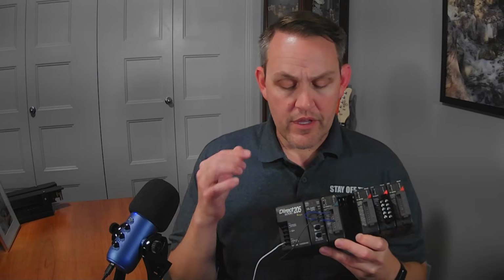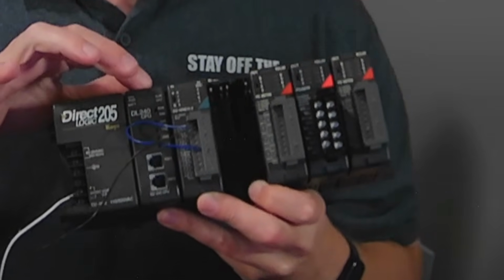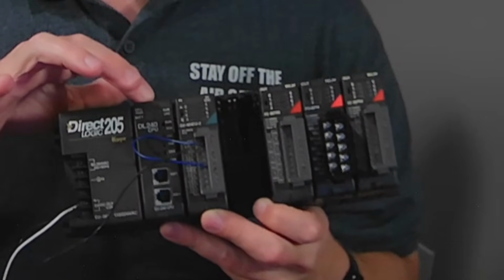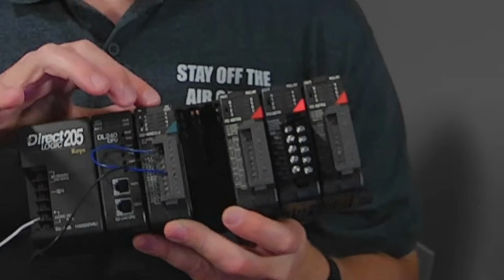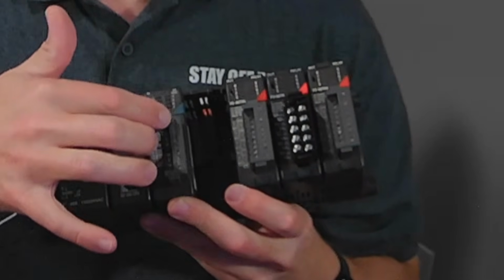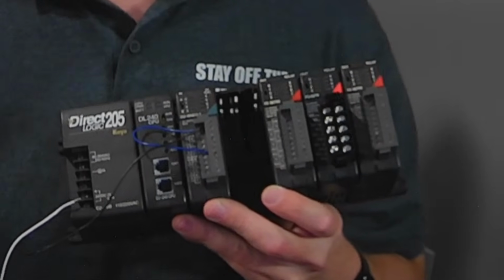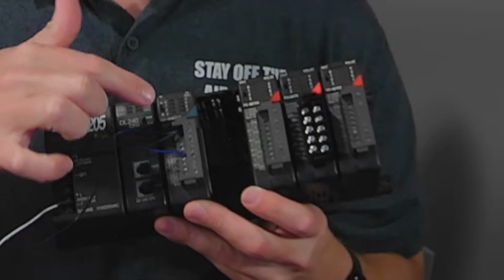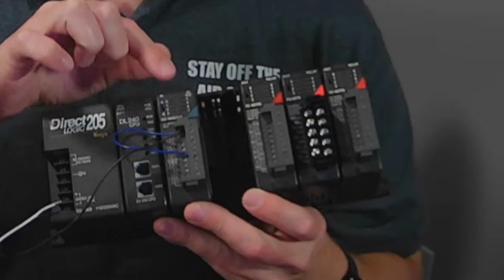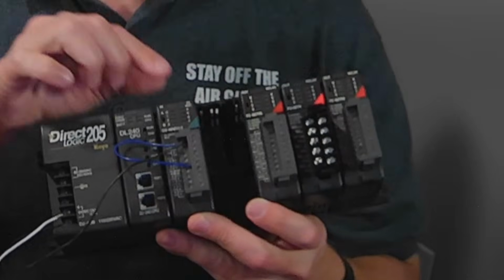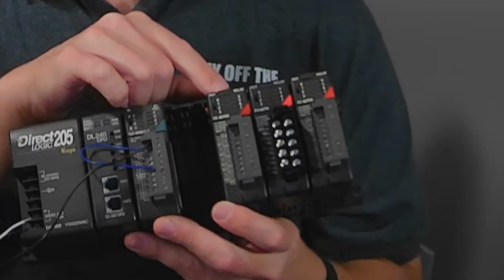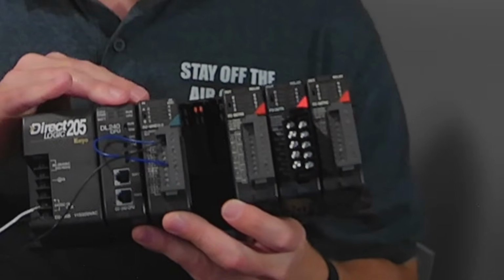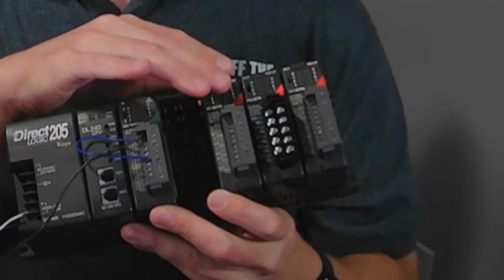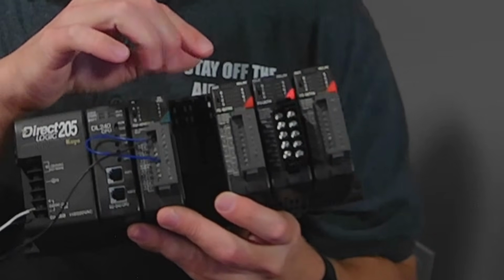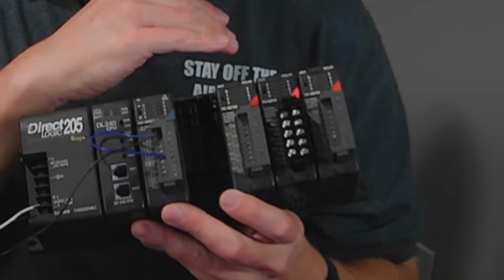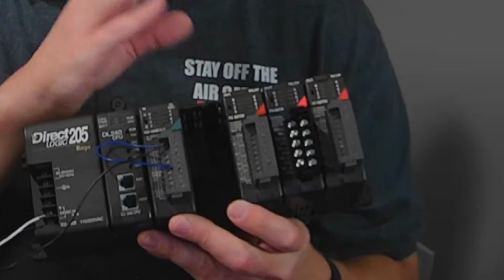So we'll start with the processor. The processor is the thing that actually has the program loaded into it that you can manipulate your I/O into making real-world decisions. Next, we're going to have the inputs. The inputs is what you hook up to a device and say that when a sensor or something along the track turns on, it's going to put an input signal into this card, and then the PLC understands that that device out there has now turned on. And last, we have the output module. The output module is once the PLC has made its decision to activate something, the outputs are what is activated. So in this case, we could use an output from here to trigger another relay or a motor or something along those lines that makes something move out on the track.